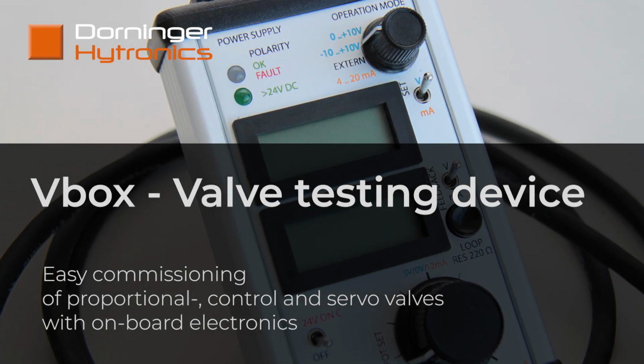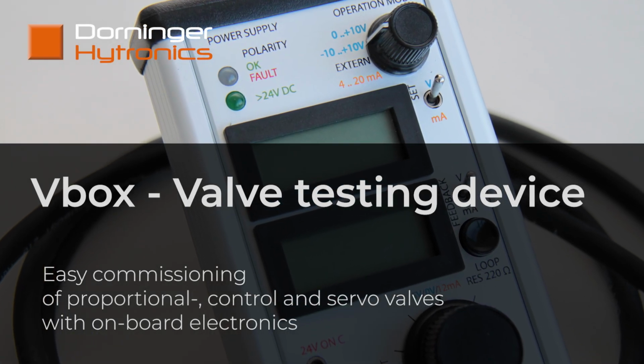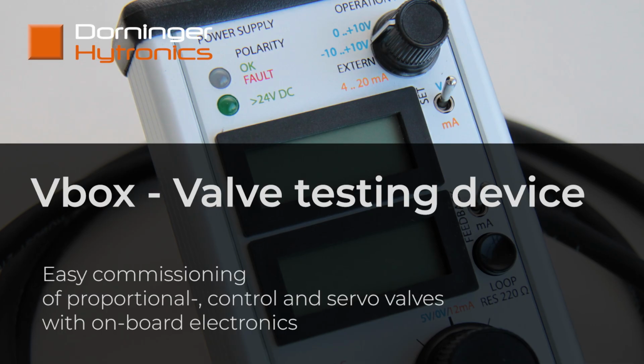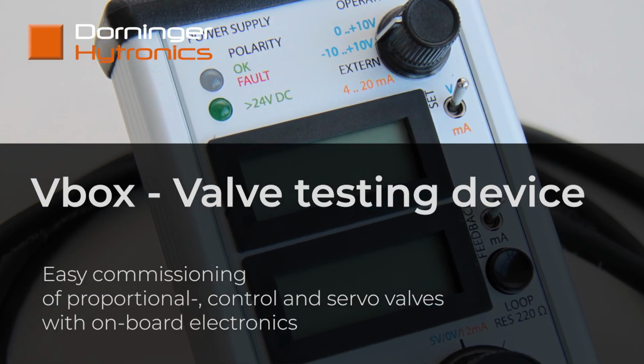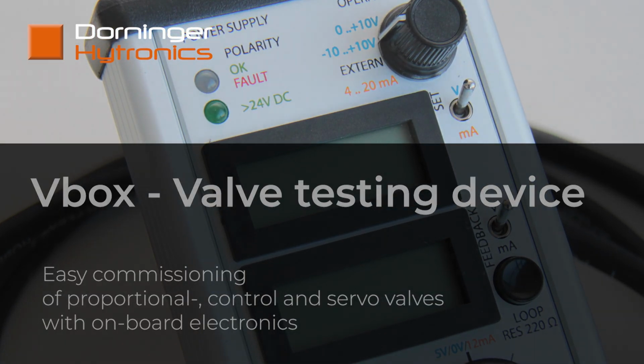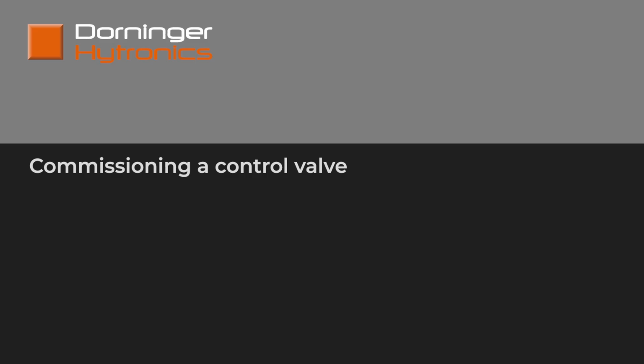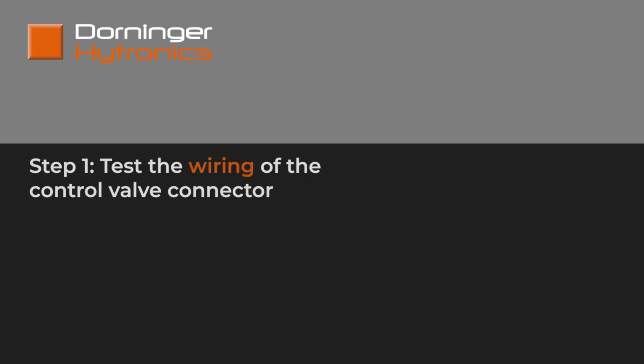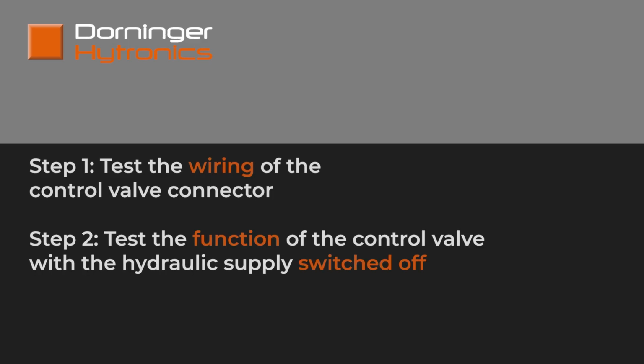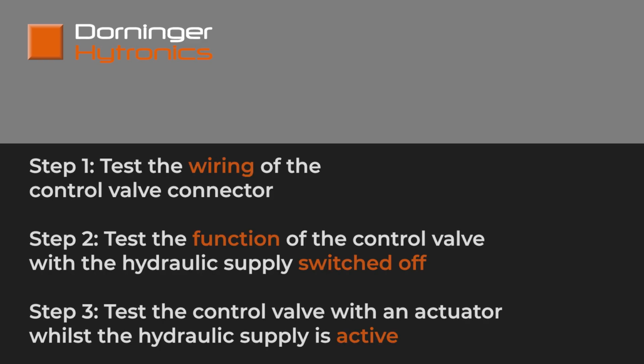In this video, we demonstrate how to use our Vbox, the valve testing device for commissioning proportional, control, and servo valves. The test has three main objectives. First, we verify the correct wiring of the valve connector between the PLC and the control valve. Second, we test the function of the control valve with the hydraulic supply switched off. And third, we test the control valve with the hydraulic supply active, for example in combination with a cylinder.